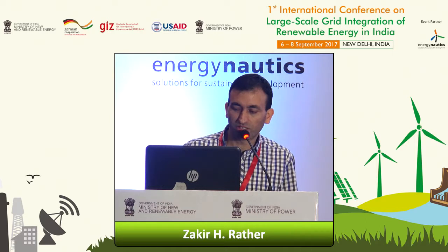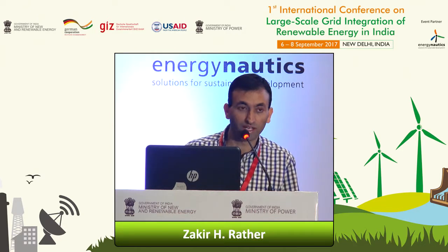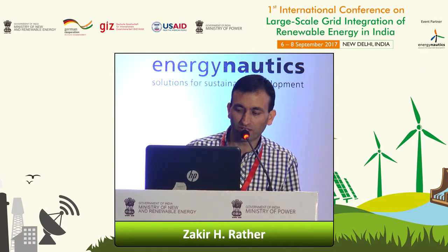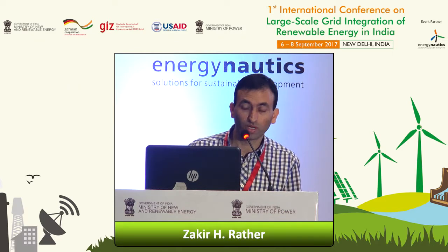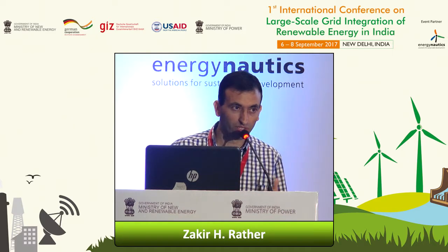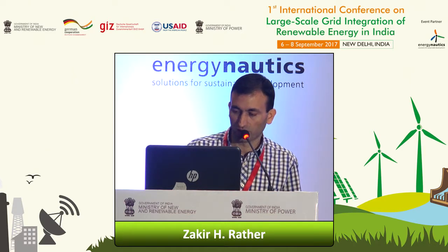So these are a number of studies we tried to capture in this plot. We have different penetration levels and try to see here how the nadir behaves. As a general trend, for the same outage, the nadir point is going to increase as we go for higher penetration of wind, and the trend is again similar. With only inertial control, we have a better nadir, but we have a longer frequency recovery time, while with both droop and inertial control, we have a better nadir as well as better frequency recovery. This recovery is relatively faster than this.